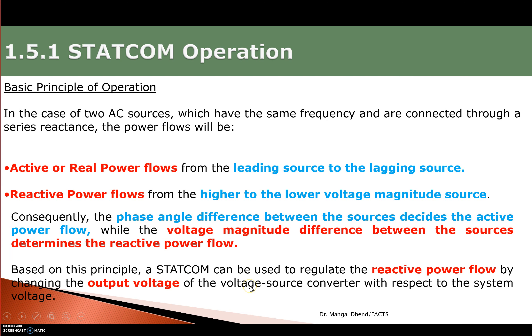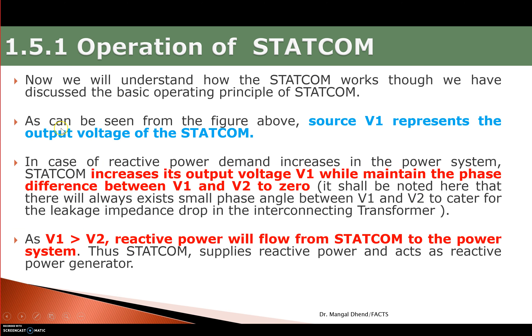Based on these two principles, STATCOM can be used to regulate reactive power flow by changing its output voltage, and real power flow by controlling the phase difference. Reactive power flow is controlled by output voltage control, and real power flow is controlled by phase difference control. The output voltage of STATCOM is represented as V1, as discussed in the earlier session.